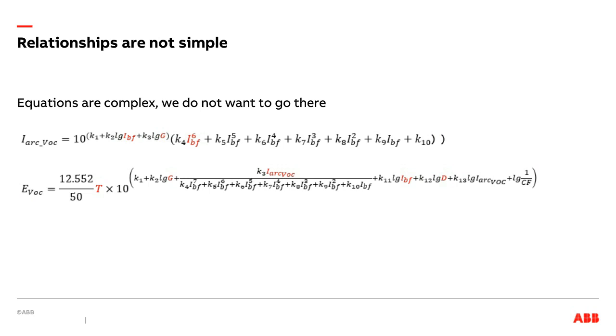The equations for all this are actually quite complex, or complex looking. When you come to programming this, like in Excel, actually, it's not that complicated, and it's quite doable. But there are a lot of equations, a lot of steps, a lot of logic in deciding what you do, when, and how. And that's not something that is typically accessible to the typical worker. If you have an arc flash study, all that is done by your software. If you have an Excel spreadsheet that does this for you, it's all done by the calculations in the spreadsheet. But typically speaking, your average worker who's looking at risk for a task either had this done and handed to him, put on the arc flash label, or it's out of his access.